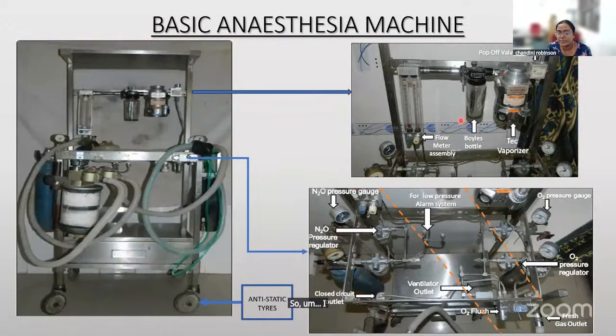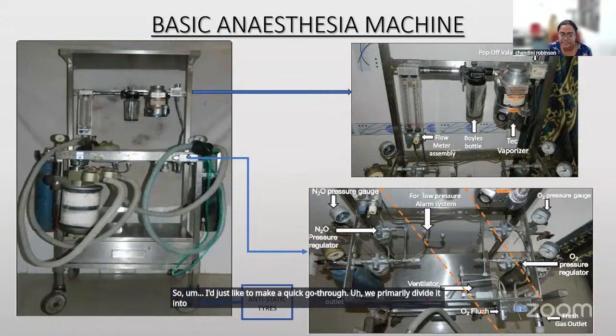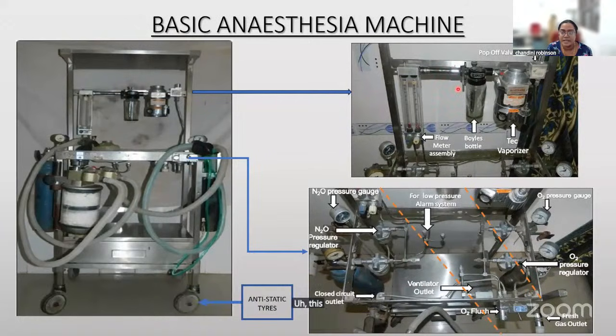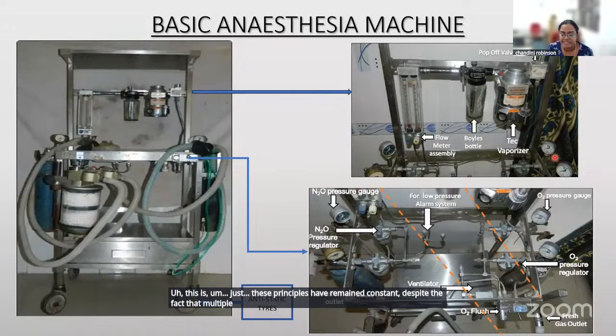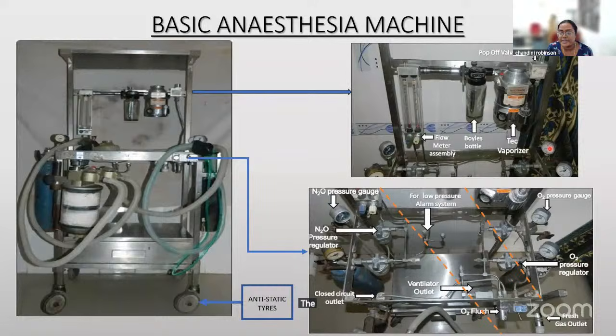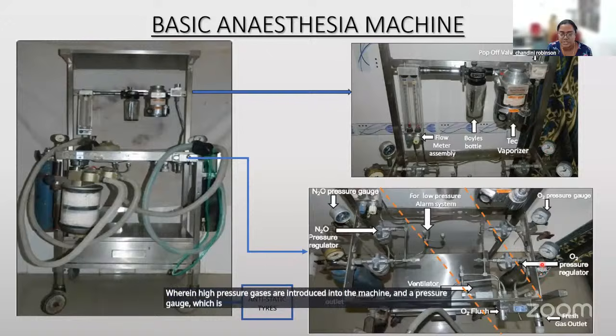I'd just like to make a quick go through. We primarily divide into a high pressure, intermediate pressure, and low pressure system. These principles have remained constant despite the fact that multiple innovations have come in. The high pressure system consists of the hanger yoke assembly, the cylinders wherein high pressures of gases are introduced into the machine, and a pressure gauge which is used for accurate assessment of the pressures.